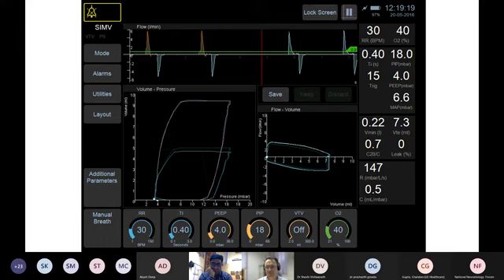So the rise of flow sensors does allow us to start controlling the amount of volume that we're delivering to the patient, which is appropriate for the size of that infant and their pathology, using modes such as VTV or volume guarantee, terminologies you might be familiar with. The flow sensor also started to allow us to be much more sensitive in triggering machine breaths delivered to the patient.